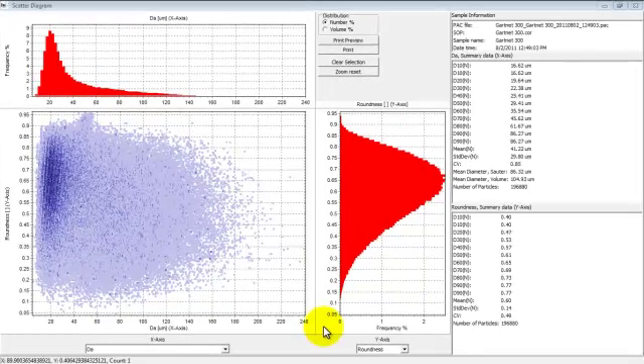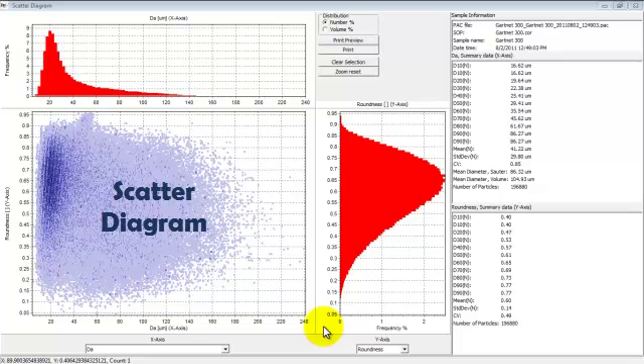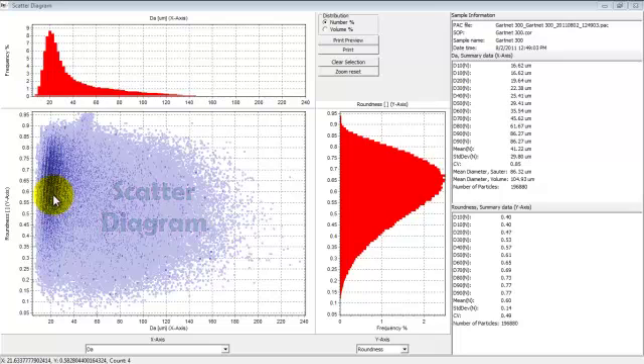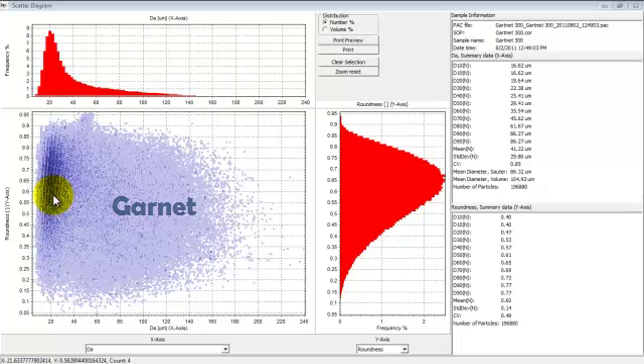This is a view of another data display called a scatter diagram — the blue graph. The location of every particle measured is shown relative to the parameter on the x-axis and the parameter plotted on the y-axis. The darker areas are areas of higher particle concentration. This data is for a garnet sample, the same that was shown in the XY graph display and in the View Particles tab. Any of the size and shape parameters can be displayed on either the x- or y-axis by choosing them in these windows.